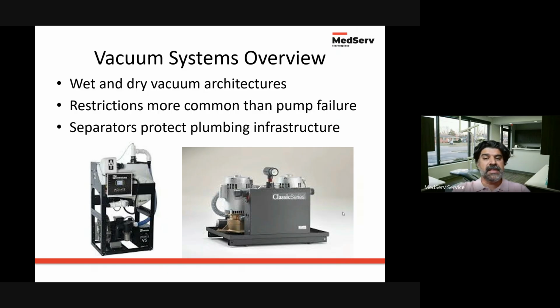So maintenance on this piece of equipment is important, and you'll hear complaints that the suction feels weak, or that the pump is louder than usual, or the system is running constantly. Those are indicating to you that there's a leak somewhere, or that the power isn't being delivered to the vacuum motor itself at the right rate in order for it to properly operate, or that there may be some sort of cloggage or blockage in the piping itself too.